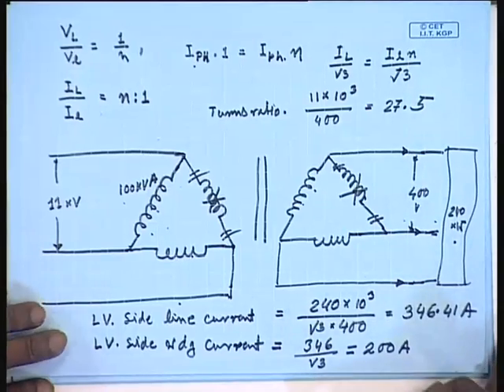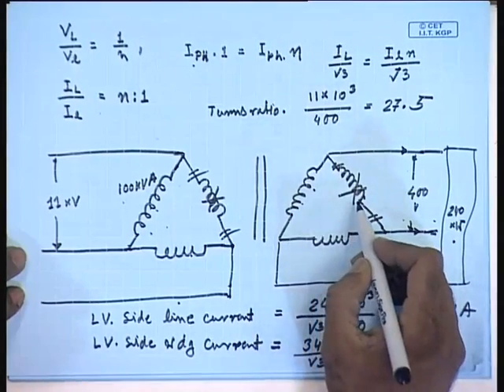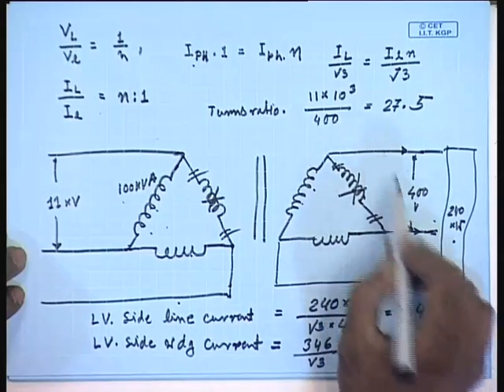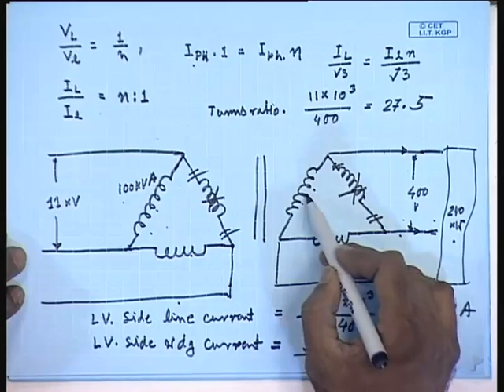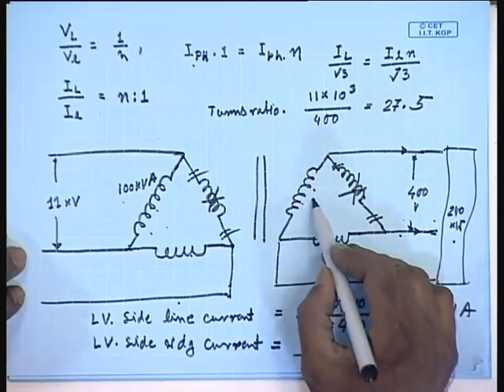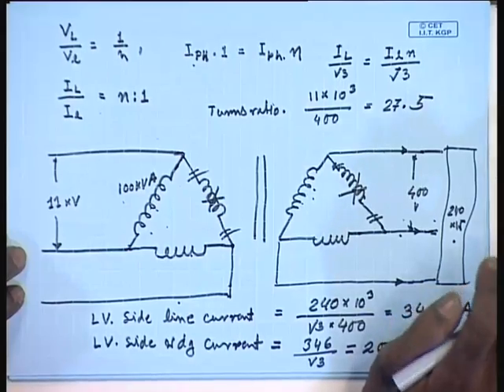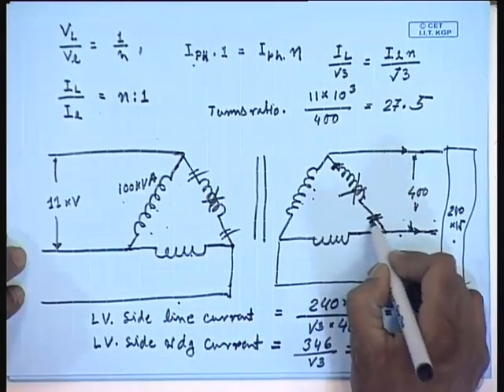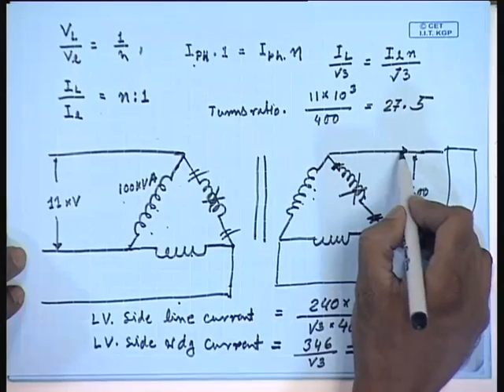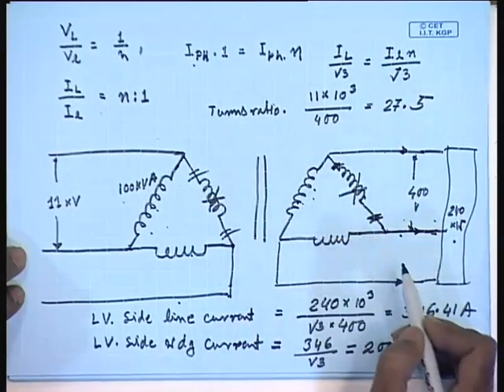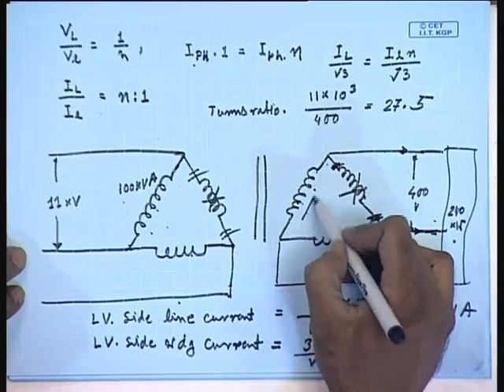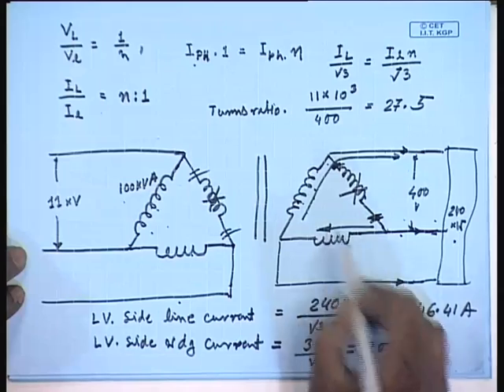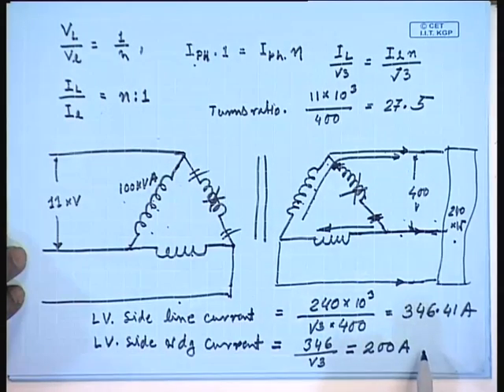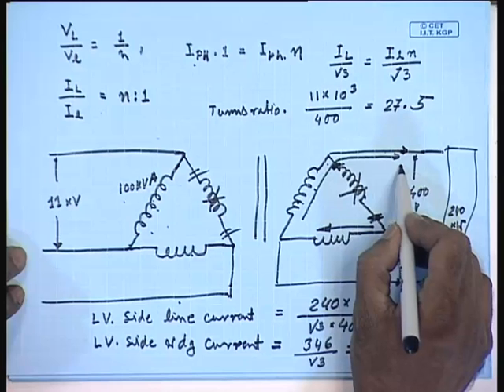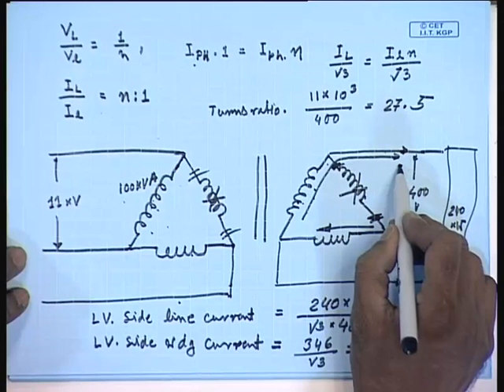So, when you are supplying this transformer with open delta connection, the LV side winding current should not exceed 250 amperes. However, it is easy to see that with open V connection the line current on the LV side is the same as the phase current, because this winding is not there. This line current flows like this and comes back through this. Similarly for the HV winding. Therefore, the line current during open delta or V connection should not exceed 250 amperes.